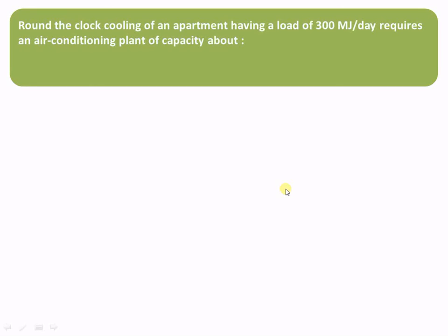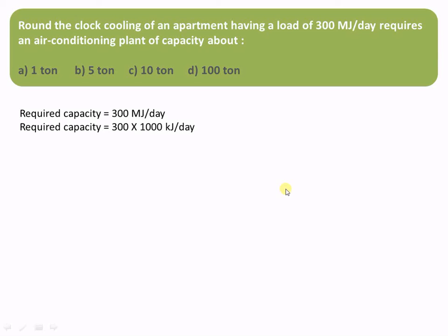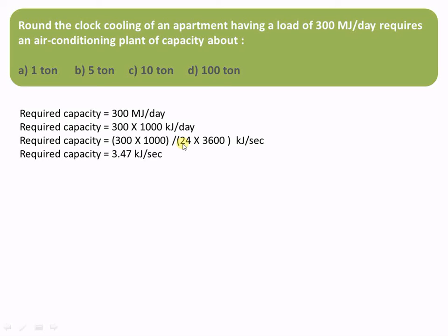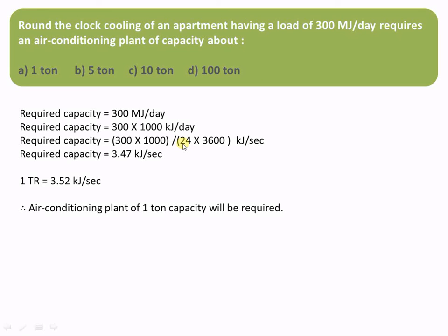In the next example, we have an apartment with a cooling load of 300 megajoule per day, and we need to find the ton of refrigeration (TR) capacity of the plant. Converting 300 megajoule per day to kilojoule per second: multiply by 1000 to get kilojoule, then divide by 24 × 3600 to convert per day to per second, giving a required capacity of 3.47 kilojoule per second. Since one ton of refrigeration equals 3.52 kilojoule per second, approximately one ton capacity of the air conditioning plant will be required.